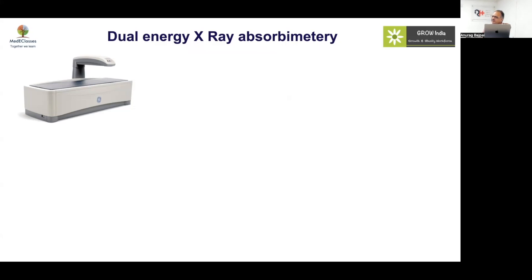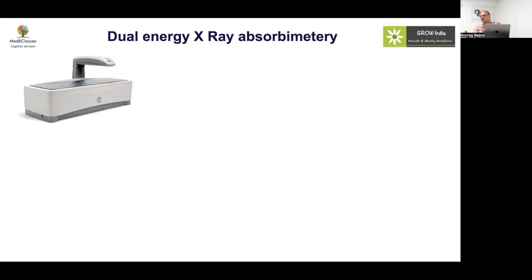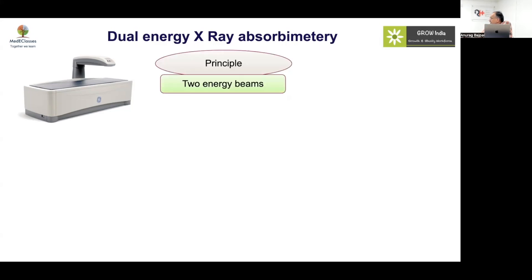Unlike a conventional X-ray which uses a single beam, DEXA uses a dual beam. The attenuation constant — how much of the beam is absorbed — differs for fat, muscle, and bone. By using two different energy beams, one high-energy and one low-energy, and differentiating their attenuation, you get a much better picture. It's based upon two different energy beams with differential uptake.